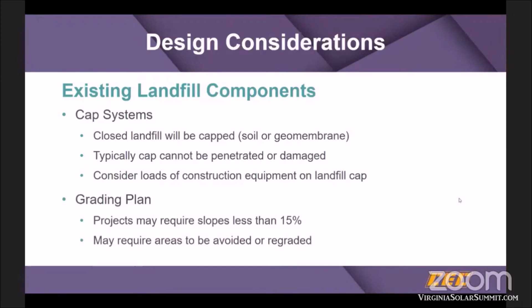Some of the primary design considerations are addressing the existing cap system of a landfill and the existing grades. Depending on when the landfill or CCR impoundment was closed, the site could have a soil or geomembrane cap system. Cap integrity is key, so maintaining the cap must be addressed. Also, solar developers often prefer slopes less than 15%, so steeper areas may need to be avoided or regraded if feasible.